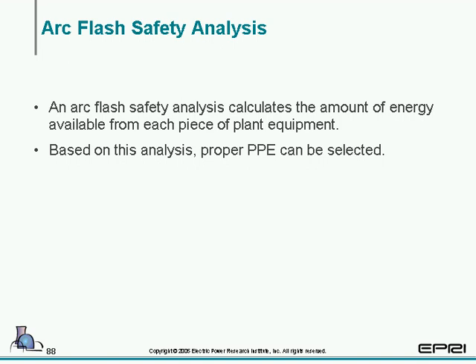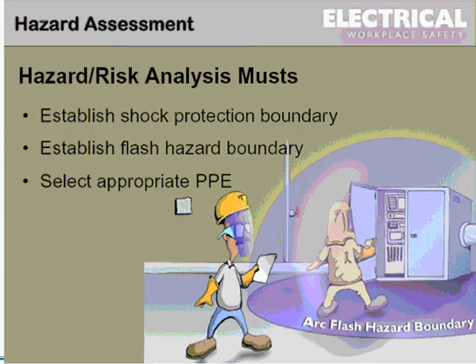I mentioned arc flash safety analysis. This is an engineering evaluation that calculates the amount of energy available from each piece of plant equipment. Based on this analysis, proper personal protective equipment can be selected.